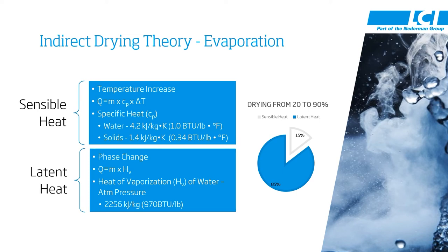Once we have the sludge at boiling, we can switch to latent heat. This is the phase change — this is where we're taking the water and turning it into vapor. In this case we use Q, again heat, equals mass, but this time it's the mass of the evaporated water, and we multiply it by the heat of vaporization, HV, of water. Once we have the latent heat, we add it to the sensible heat to get the total heat. The pie graph shown here demonstrates that the vast majority of heat required to evaporate water is in the form of latent heat.